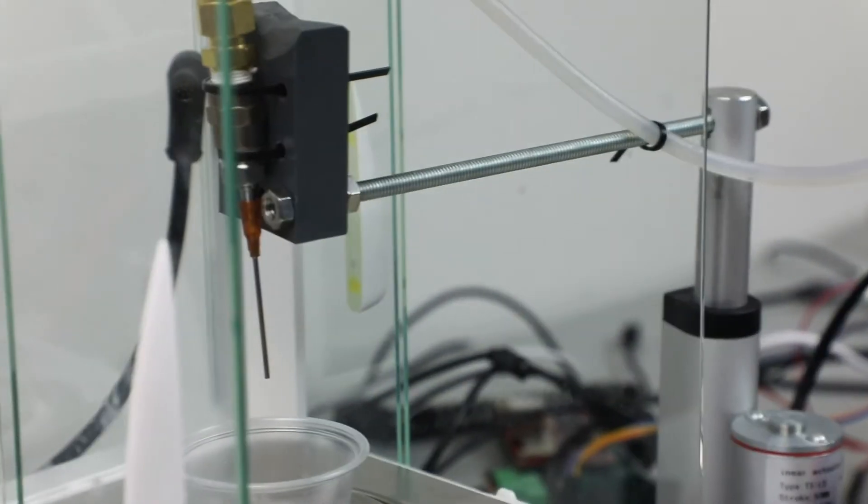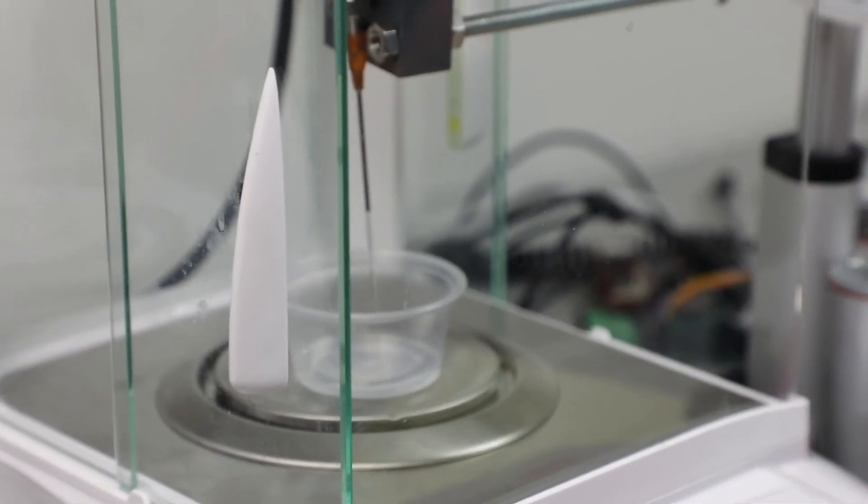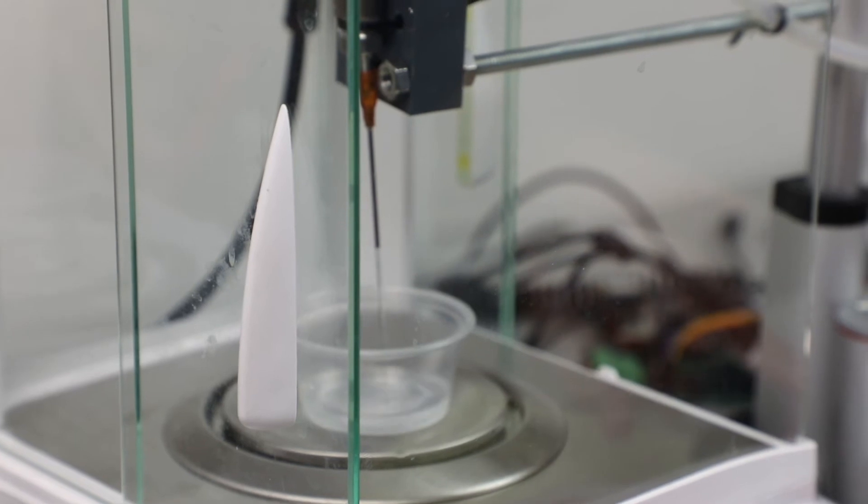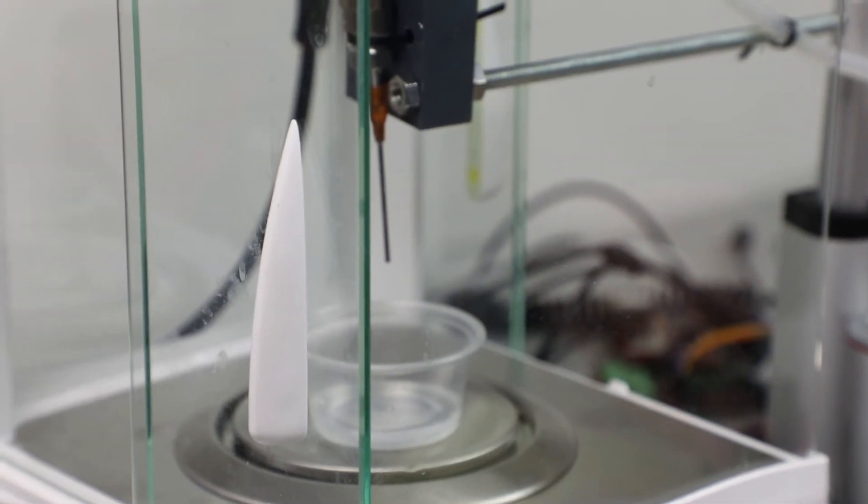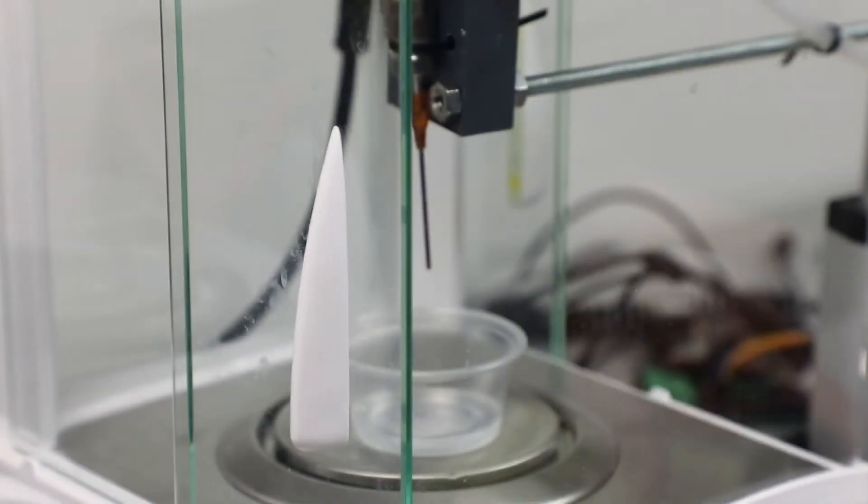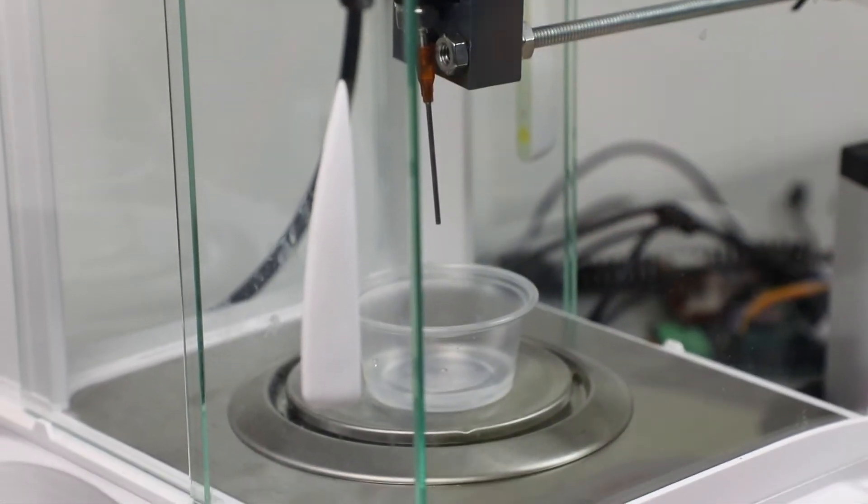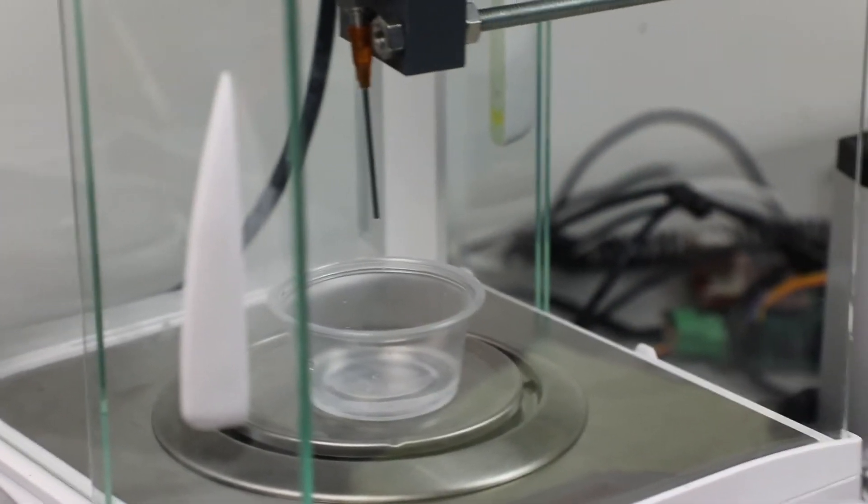It's going to shortly be here. It's coming up now through the pump. And the idea of the slow speed is to, and at maximum, allows us to kind of uniformly move fluid through, not introduce air bubbles into the system. Once my system is primed, I can pause or hit the abort. I then can go back to my dispense mode. Let's say I need to do one dispense of this 0.1. I hit my equals.